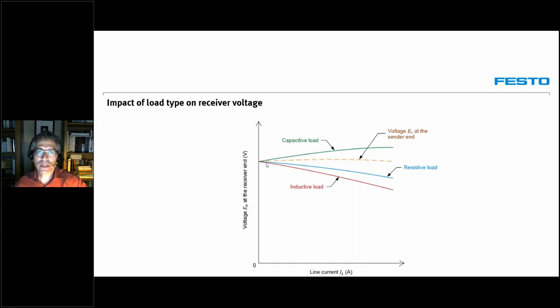But if we connect a capacitive load at the receiving end of the transmission line, we will see that the received voltage will increase as the load increases. So the larger the capacitive load, the more voltage we will get at the receiver end. While with a resistive load, we will have a decrease in received voltage, and for an inductive load, an even bigger decrease in received voltage at the other end.